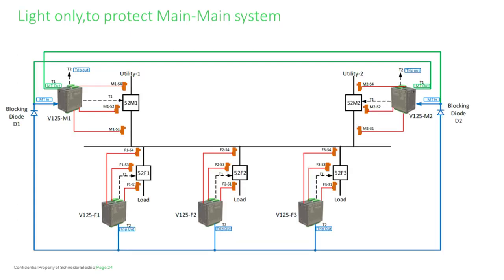Let's look at a sample main-main system — a single bus. This shows how we apply the light-only system. If any fault happens on the bus, we have to clear both of the main incomers. Signals are passed from the feeders up to the main incoming to clear the entire system. This should be called a one-zone system.